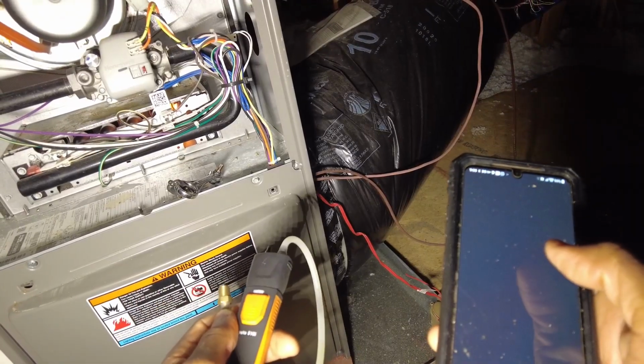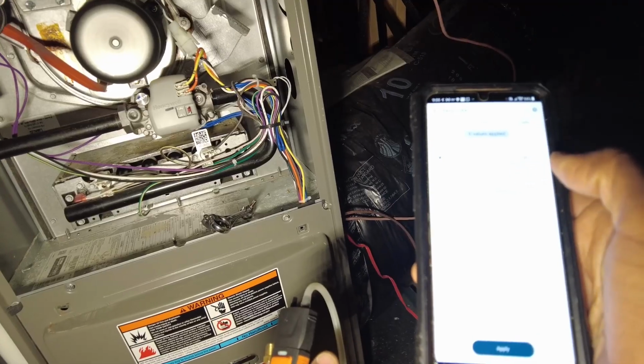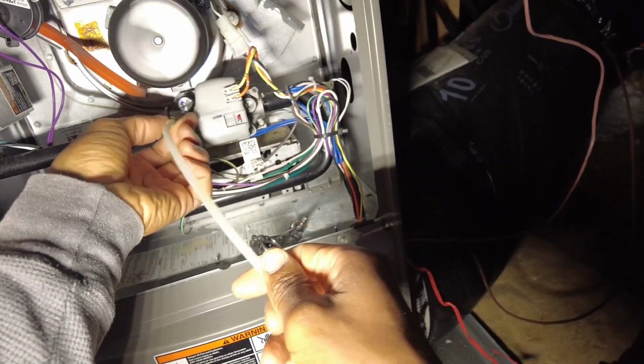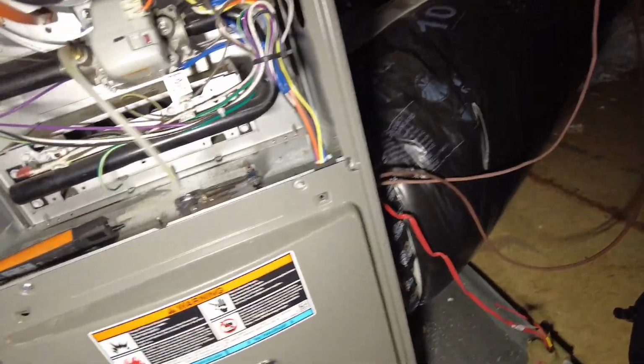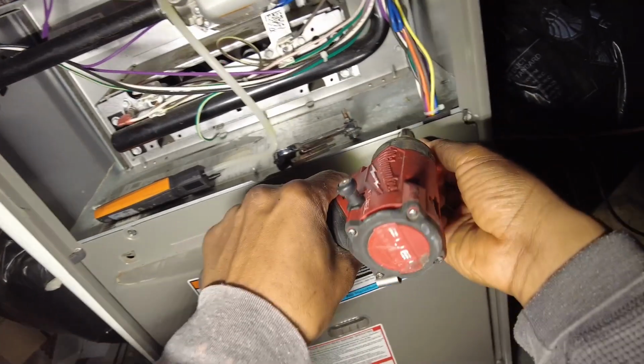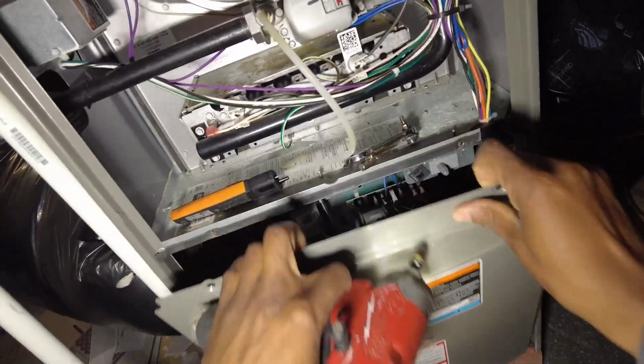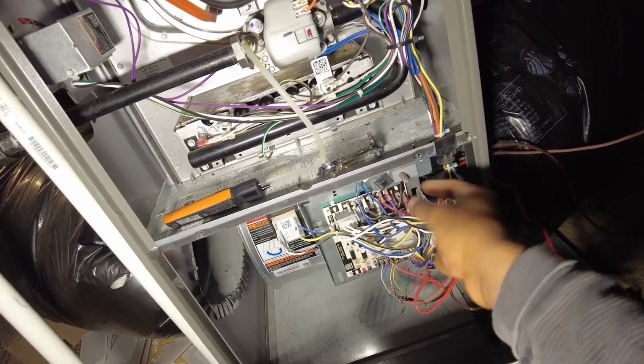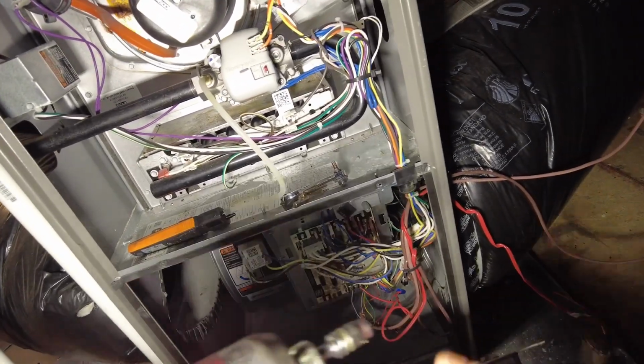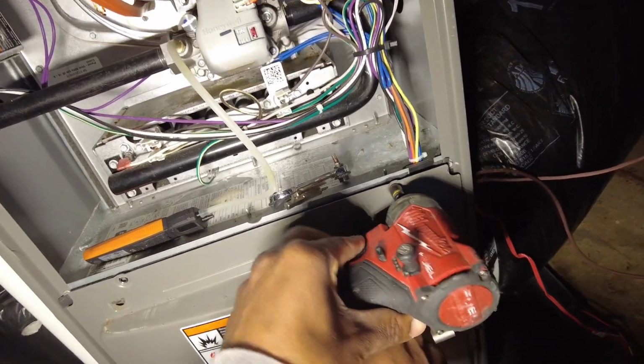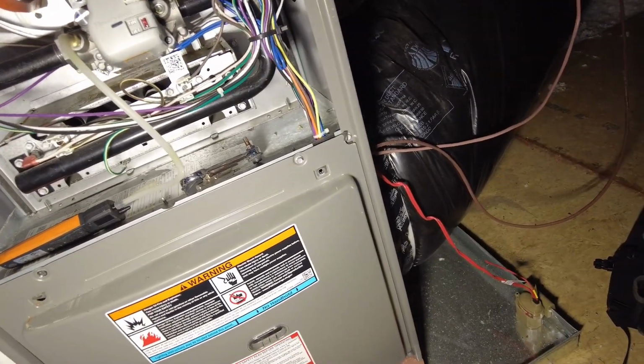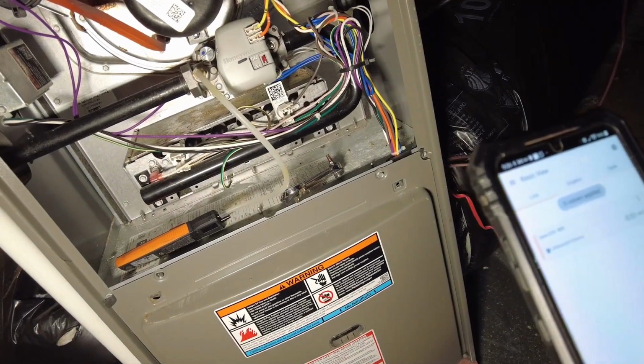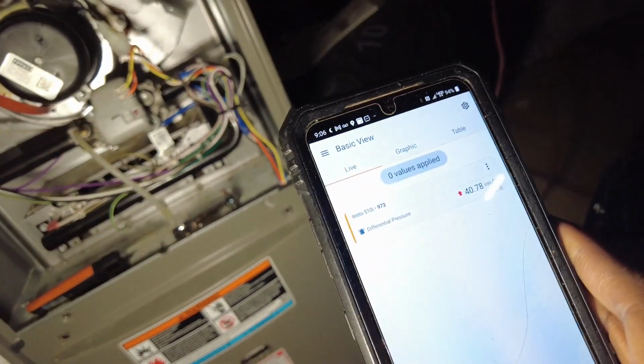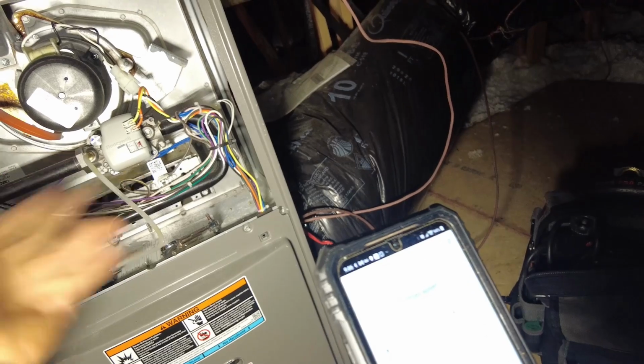Okay. Go back to our app, zero it out, zero pressure. So simply just pop this on here like such, right? So I just reset it. This little switch here, open up this power. Now it pretty much faulted out. It attempted too many tries to recycle. So now it should cut back on here. Turn our gas pressure on, you're gonna see this number go up, right? Spike like crazy. See that? 40 inches of water column. That's pretty much because it was static in the line, so now it just spiked, but it'll go down. So we're checking both this side and this side.